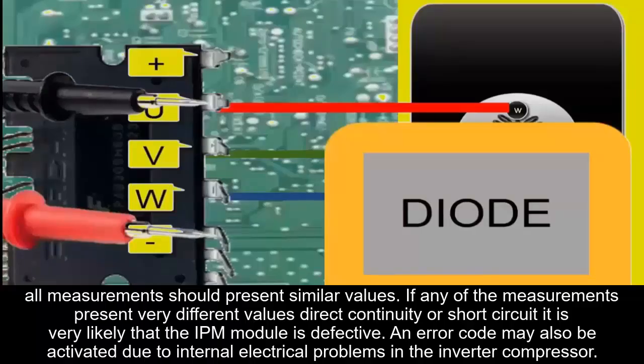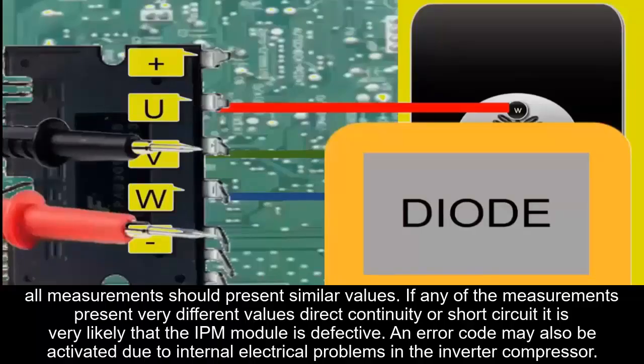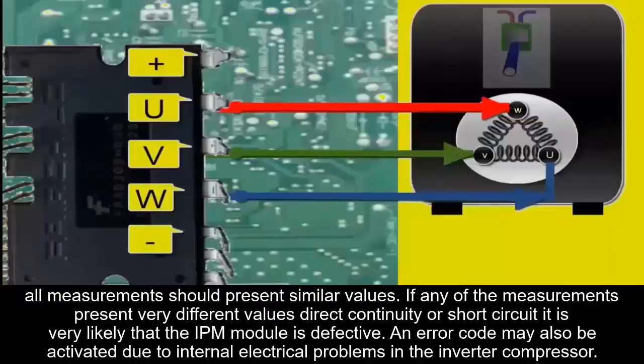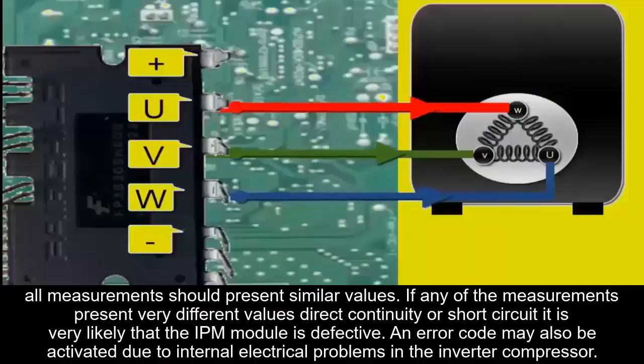If any of the measurements present very different values, direct continuity or short circuit, it is very likely that the IPM module is defective.